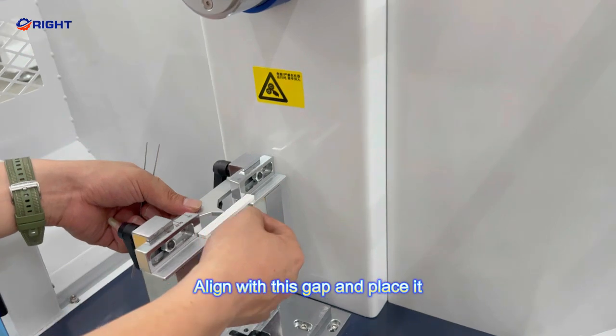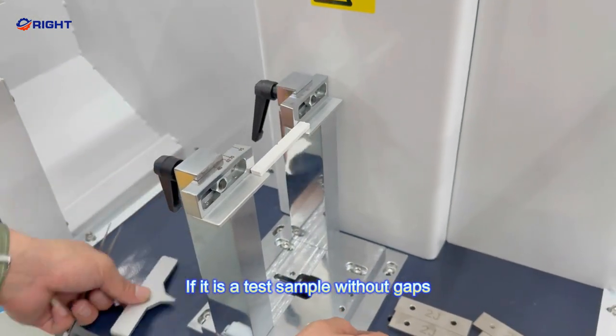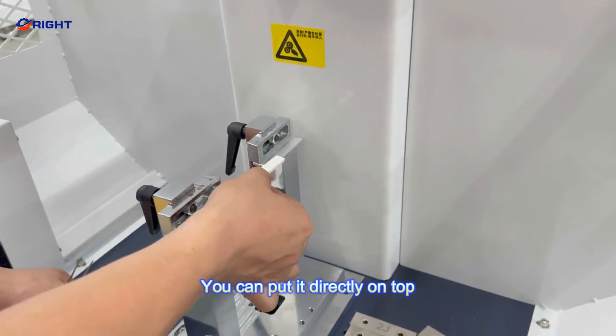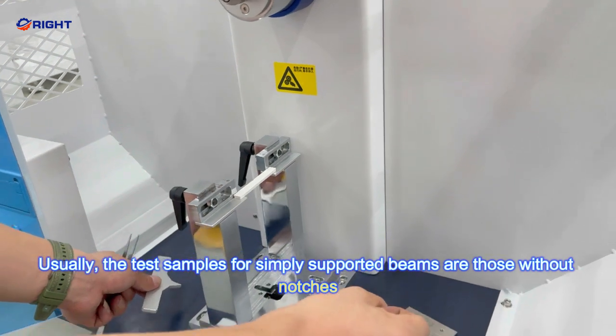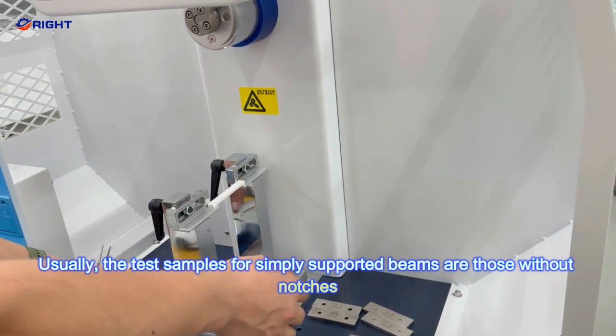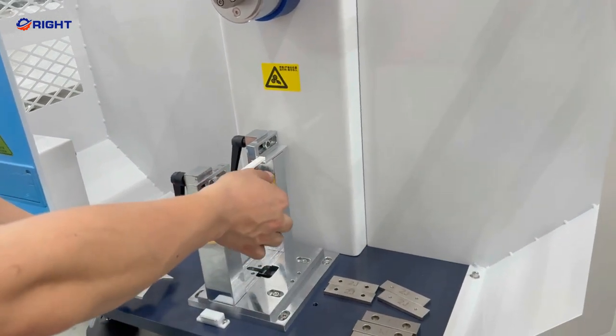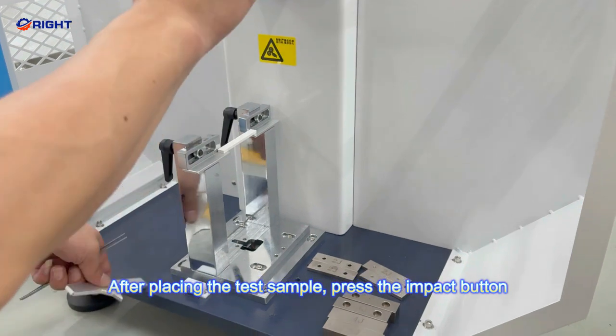Align with this gap and place it. If it is a test sample without gaps, you can put it directly on top. Usually, the test samples for simply supported beams are those without notches. After placing the test sample, press the impact button.